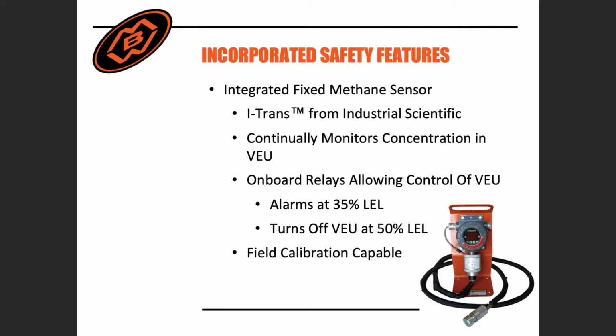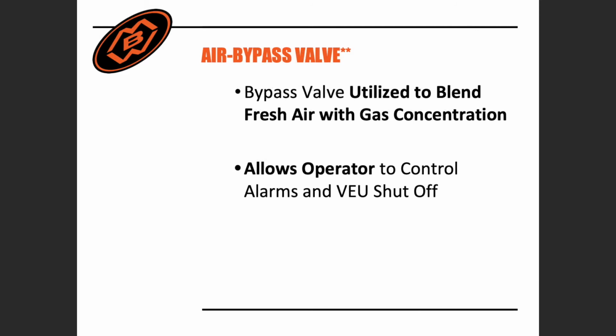We do sell the calibration kit, which comes with the regulator for the cal gas, hoses and cups to connect to the sensor for the calibration process. The air bypass valve gives the operator full control of the gas extraction process, audible alarms, and VEU shutoff.